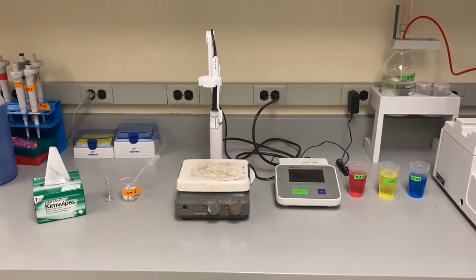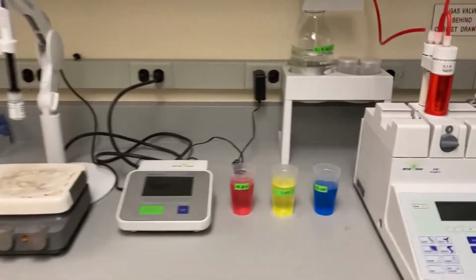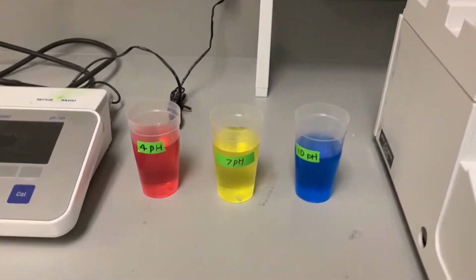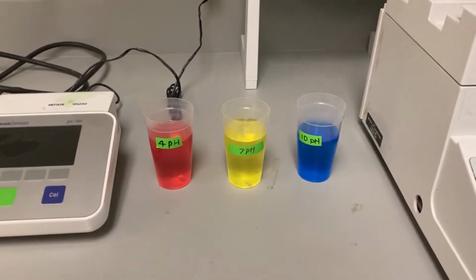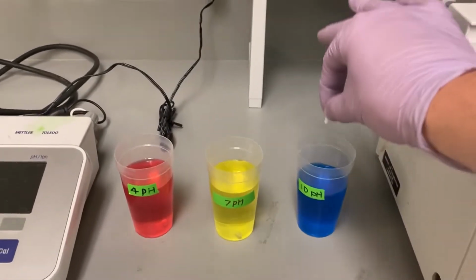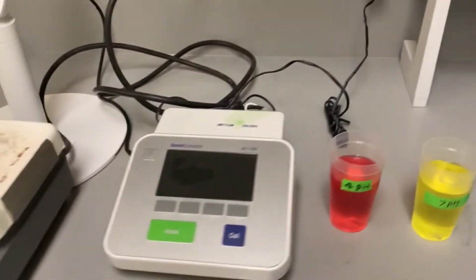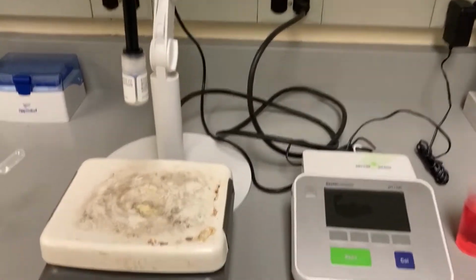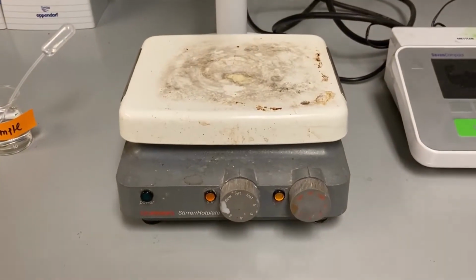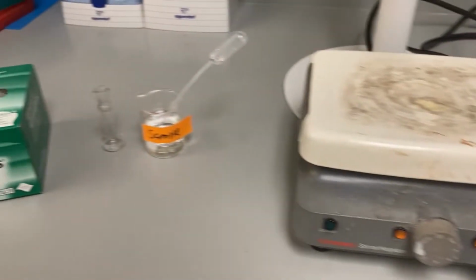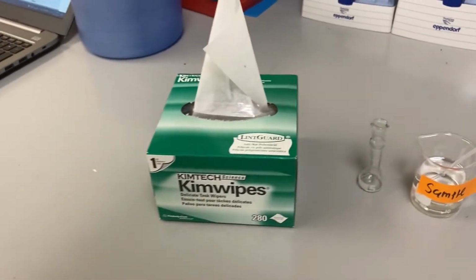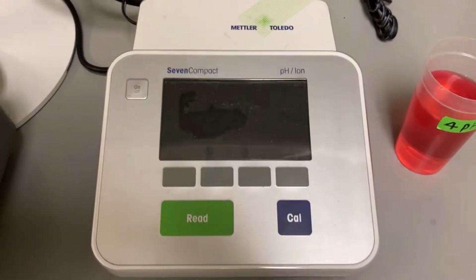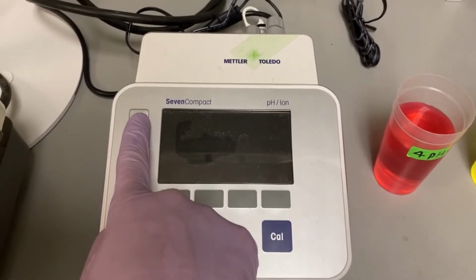To use the pH meter, you will need a pH buffer of 4, 7, and 10, and make sure that each one has a stir rod. Of course, the pH meter, a hot plate that has a stirring function, your sample, and some Kimwipes. So you can turn on the pH meter just in the top left.